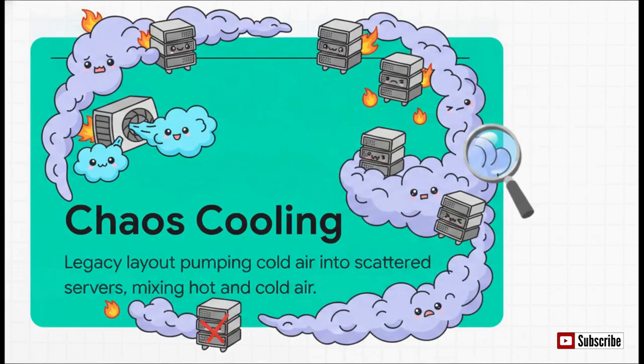Back in the day, the industry relied on a legacy approach we call chaos cooling, and yeah, it was exactly what it sounds like. Engineers would basically just blast freezing cold air from standard AC units into a giant room full of scattered servers. But here's the catch: servers suck air in through the front and blow scorching hot exhaust out the back. So if your racks are randomly scattered everywhere, the hot exhaust from one rack gets sucked directly into the cold intake of the rack right behind it. This creates a chaotic, messy cloud of mixed hot and cold air, which completely destroys your thermodynamic efficiency and sends that PUE metric absolutely skyrocketing.